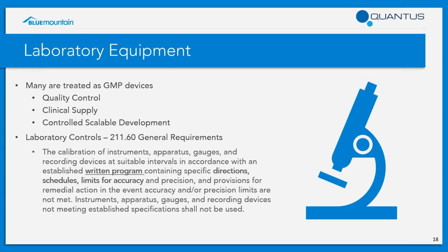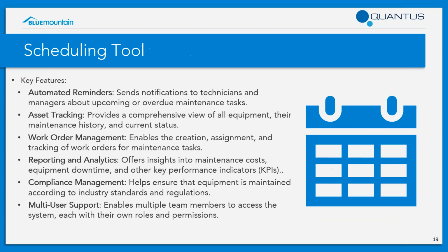I wanted to put in a quick slide here to talk about laboratory equipment. The CFRs directly talk about laboratory equipment and state that it should undergo the same level of scrutiny as manufacturing equipment. There are a lot of companies out there that will do product testing and release in GLP, QC labs. So a lot of the instrumentation that you are using is going to be just as critical as the equipment in the manufacturing facility. So the key takeaway from this particular slide is you're going to want to apply your program to each of your instruments equally throughout the facility.